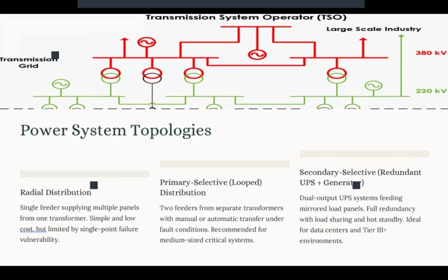We could have several topologies in our power system distribution. We could have a radial distribution, which means we have a single feeder. So there is one connection point to the external power grid. We have a single feeder, which supplies multiple panels. That doesn't mean that single feeder is directly connected to all the equipment. We said we have to have load segregation. So that feeder supplies multiple panels, and each of those panels is for a specific zone.